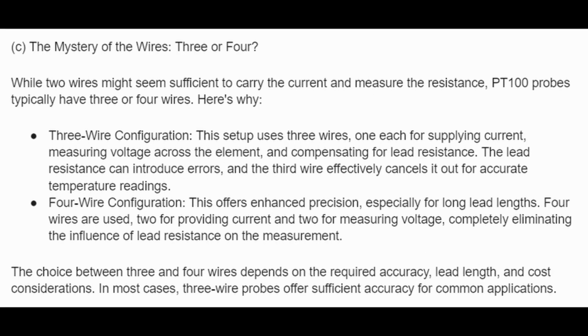C. 3 or 4 wires. While 2 wires might seem sufficient to carry the current and measure the resistance, PT100 probes typically have 3 or 4 wires. Here's why. 3-wire configuration. This setup uses 3 wires, 1 each for supplying current, measuring voltage across the element, and compensating for lead resistance. The lead resistance can introduce errors, and the 3rd wire effectively cancels it out for accurate temperature readings.